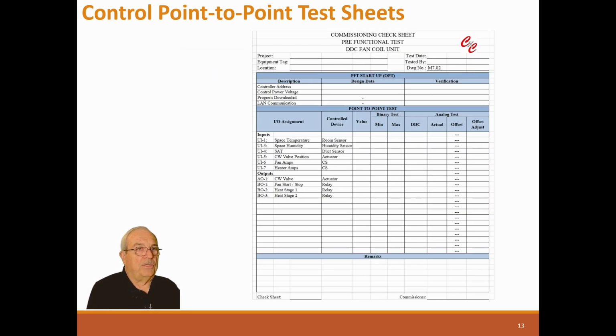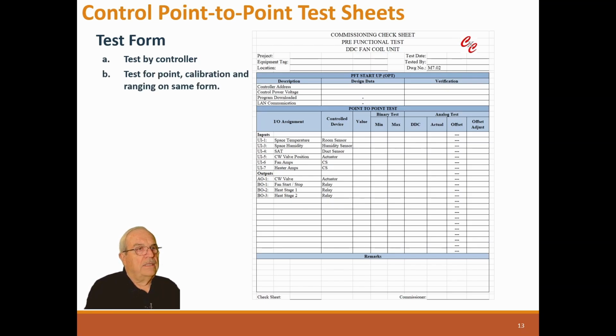Here's a control point-to-point test sheet, and we've gone over these test sheets already in the other session. Test form is tested by controller again. Test for point calibration and ranging on the same form. This is the controller data. This means what kind of controller it is. Is the network completed? Is it up and running? Here's the I/O points on the system.